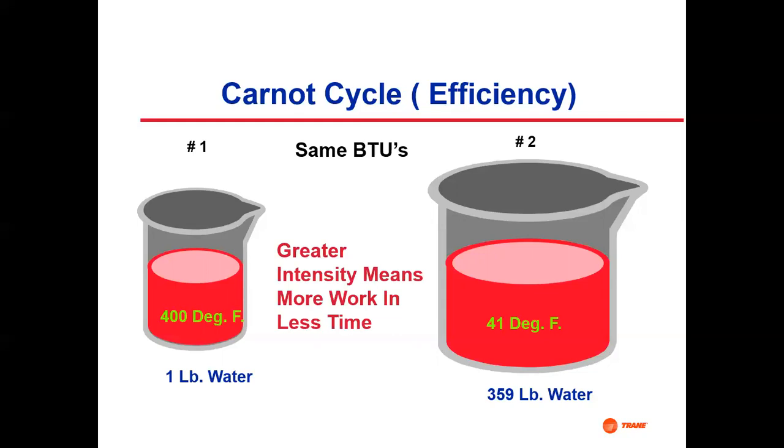Even though you're buying more hardware, so the equipment's going to get more expensive, you'd have to evaluate. There's probably more bang for the buck in a two-stage machine if you have that temperature available. But if you've got free energy at 250, oh, hell, that's single stage right there, because free energy is free, right? It's kind of in the definition. And you can't do better than that. So if all you have to do is buy the equipment, pay the maintenance and run it, and the energy input is free, that's probably going to look pretty good long term, to see what the payback is.